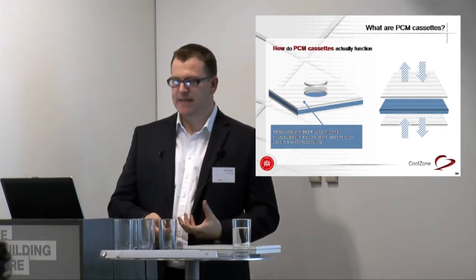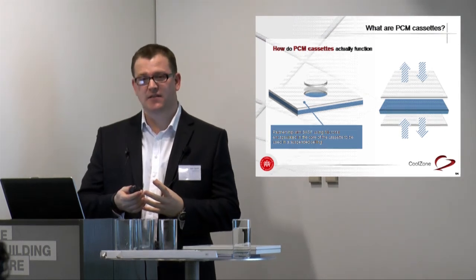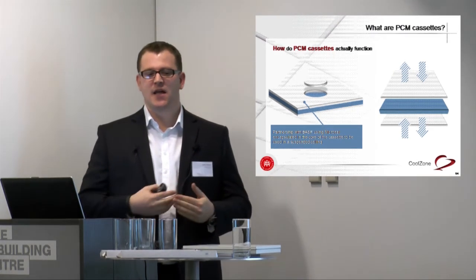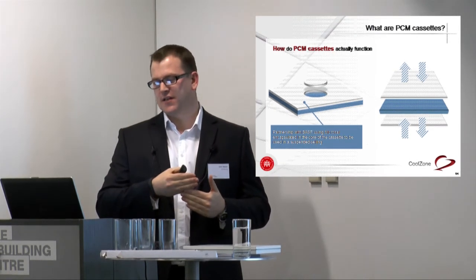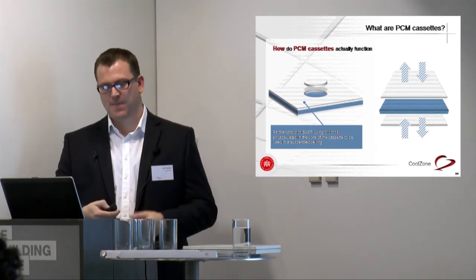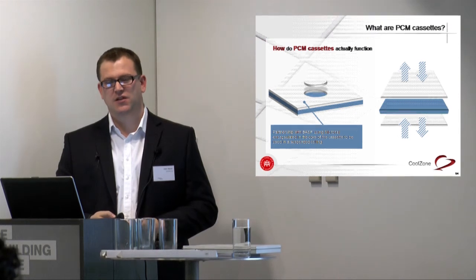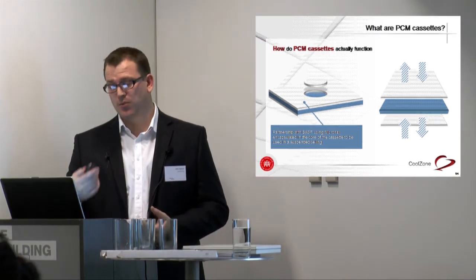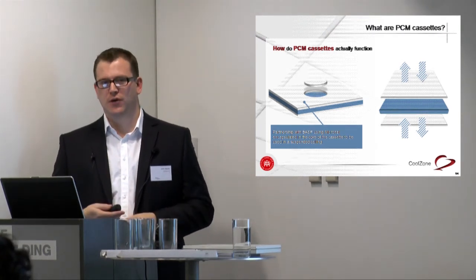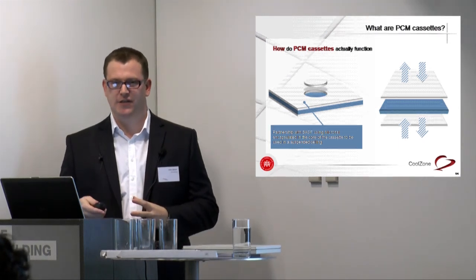On durability, the micro-encapsulation maintains the reaction so efficiency isn't lost. We've accelerated the process so one melt-and-solidify cycle, which normally takes a day, happens much faster in testing. We're already over 10,000 cycles, equivalent to about 30 years, so this product has a 30-year guarantee. It will probably continue working longer than that. We expect a change of use in the building to occur before this product actually starts losing its ability to absorb heat.